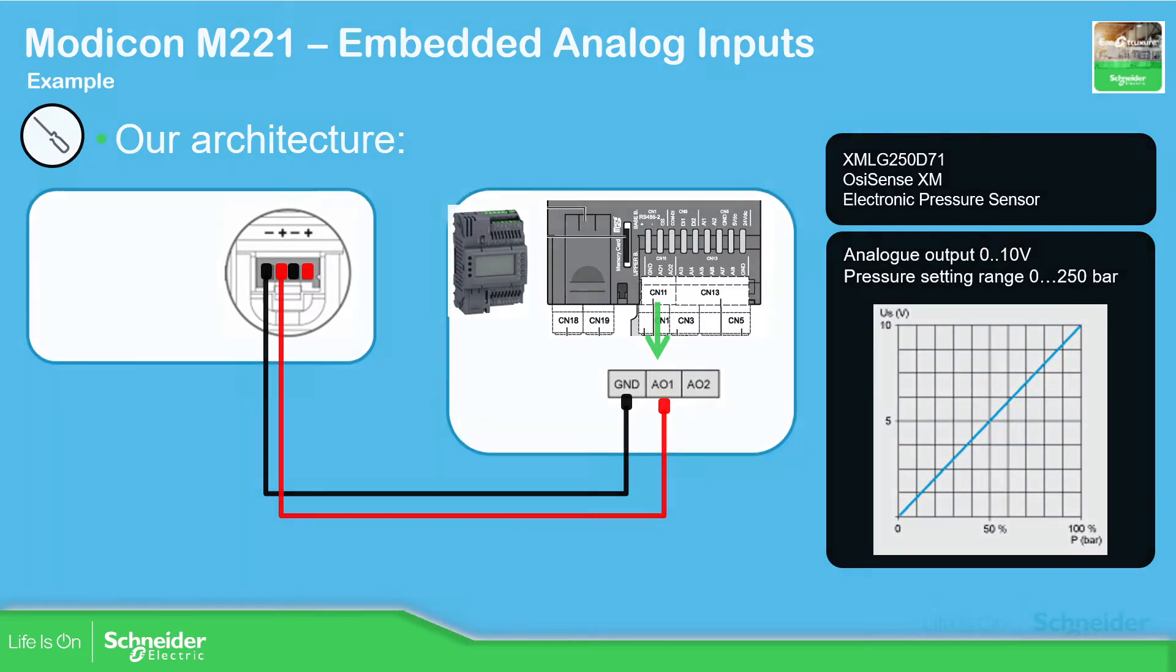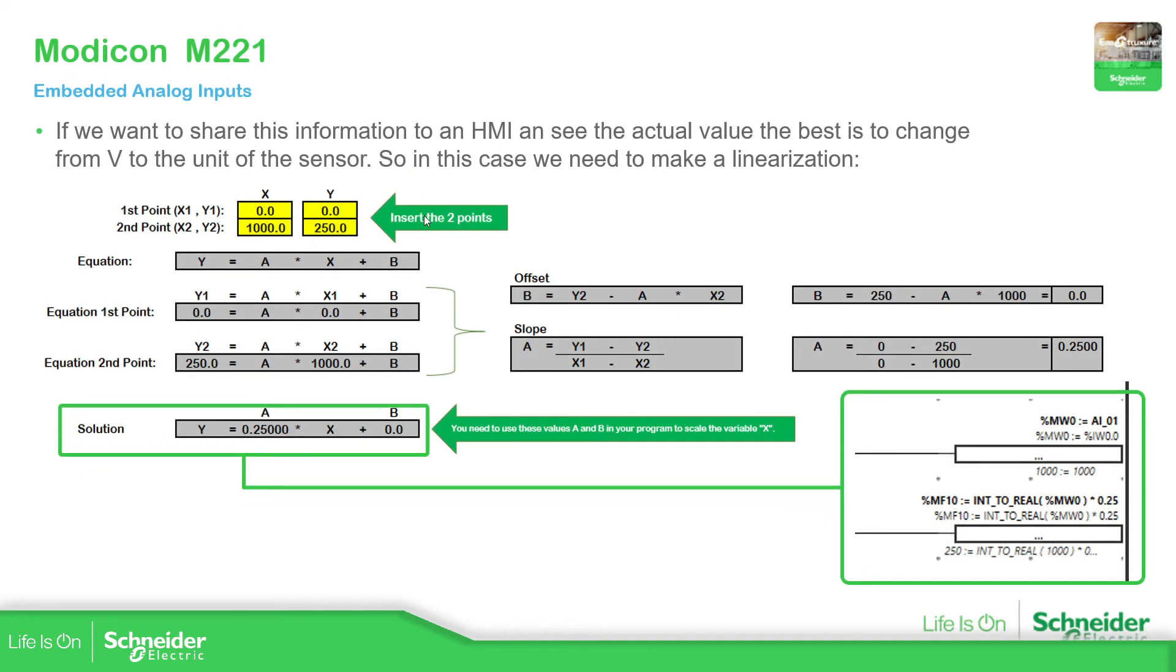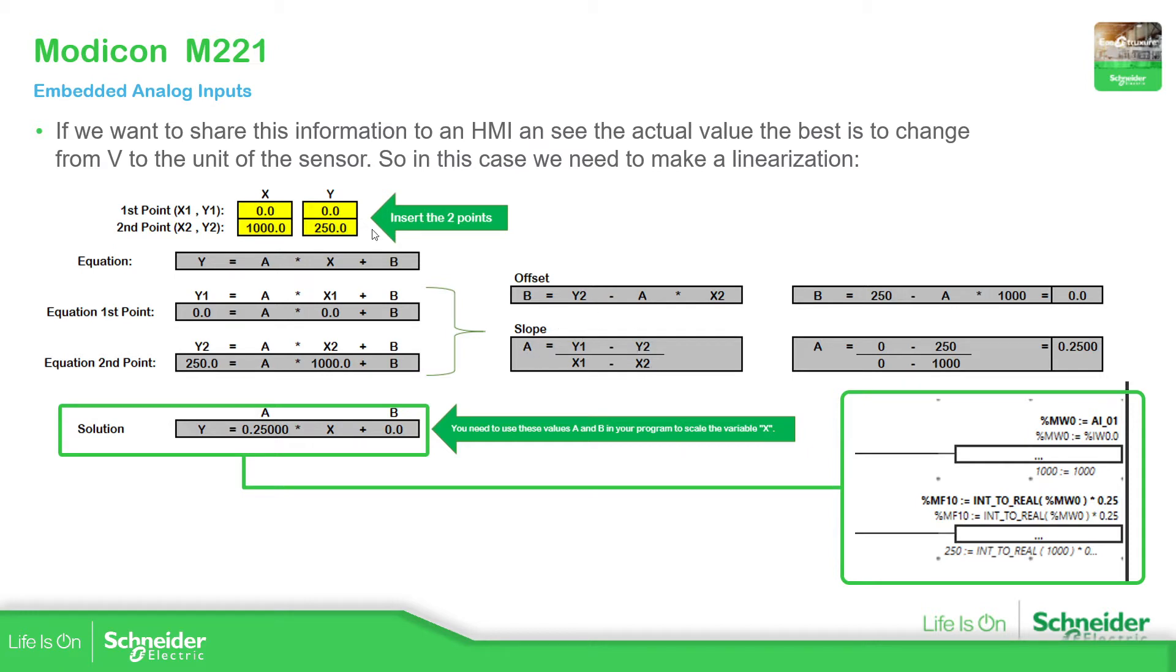In here, I'm using the linear equation. So based on two points I can calculate the offset and the slope, and I can use those values in our program to visualize the real value that I want. If you have two points you can calculate the linear, and you can calculate the offset and the slope. Here you have the formulas, so you can easily calculate this in case you want for another point or another type of sensor, it's very straightforward.